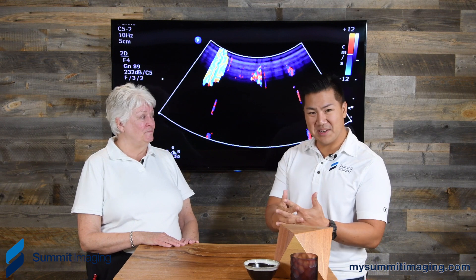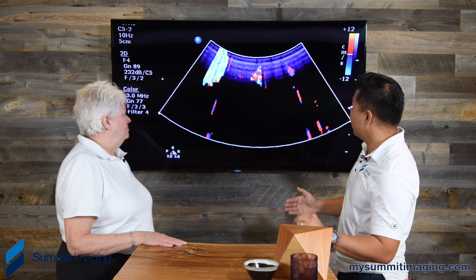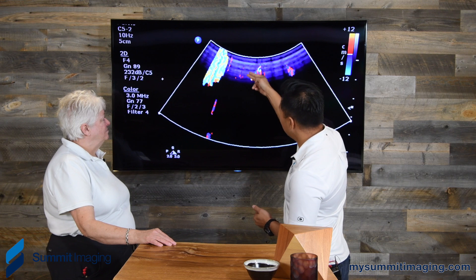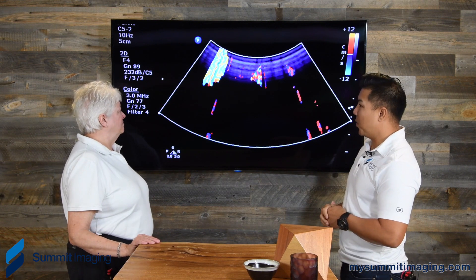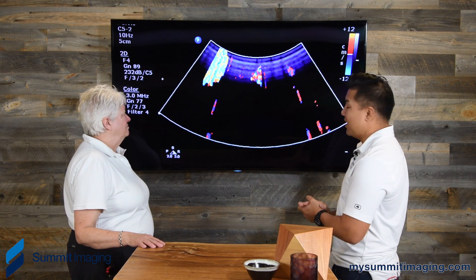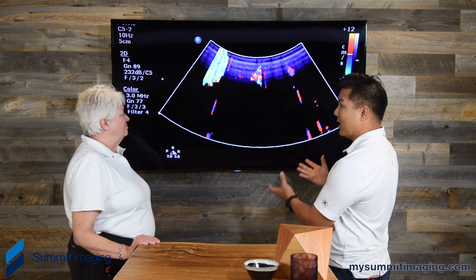She gives us so much insight into an image that is inherently blurry, and we need to understand what's good blurry and what's not good blurry, and how to get rid of it to see what we're trying to find. It's a hard art when it comes to the imaging space. Today we wanted to ask about a convex probe that had come in with a lot of color noise — these artifacts and spikes of color across the entire crystal — and get your take on the impact to the patient from an image quality perspective, and also how it impacts the sonographer capturing this image.